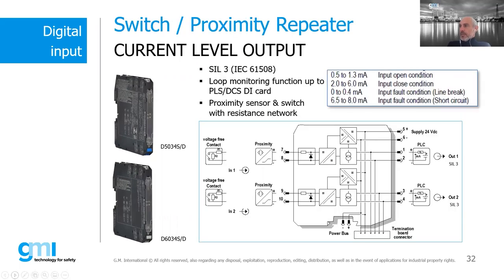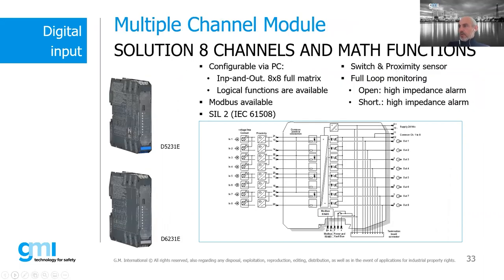Proximity sensors can also be repeated directly to the PLC. The proximity sensor gives different current values depending on the state: a simple current value for the open state, a different current for closed state, and when a line break or short circuit happens, yet another different current value. We also have multiple digital input solutions where you can have a simple straight input-to-output communication, or math functions that can be programmed.